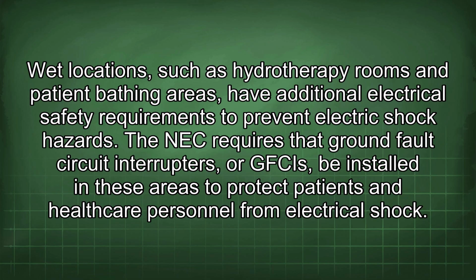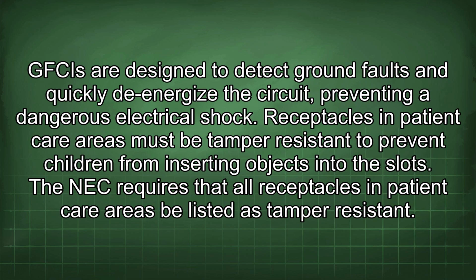Wet locations, such as hydrotherapy rooms and patient bathing areas, have additional electrical safety requirements to prevent electric shock hazards. The NEC requires that ground fault circuit interrupters, or GFCIs, be installed in these areas to protect patients and healthcare personnel from electrical shock. GFCIs are designed to detect ground faults and quickly de-energize the circuit, preventing a dangerous electrical shock.